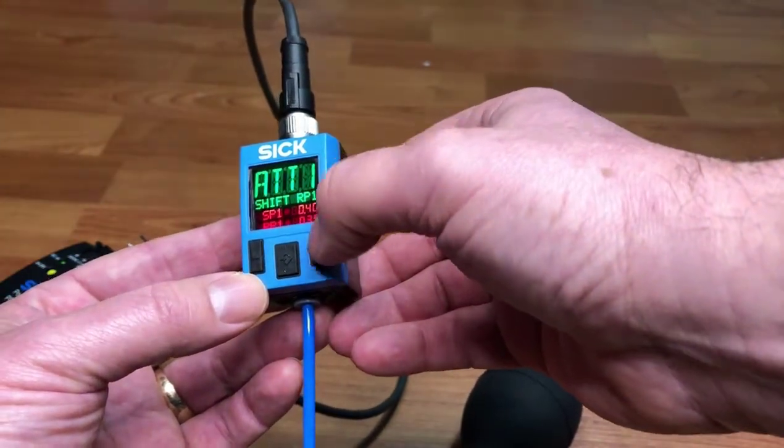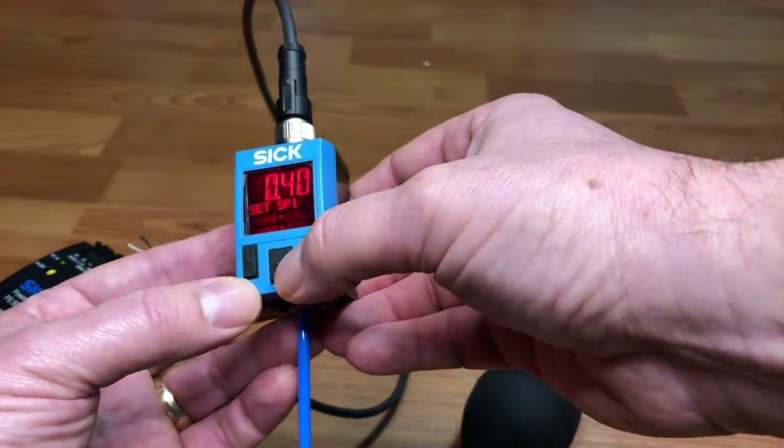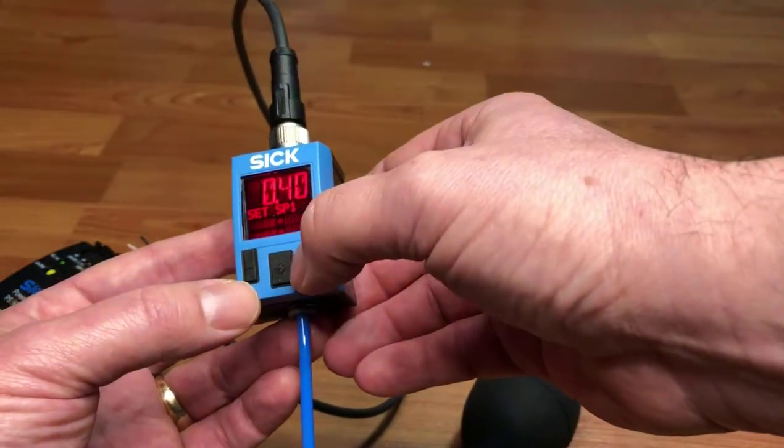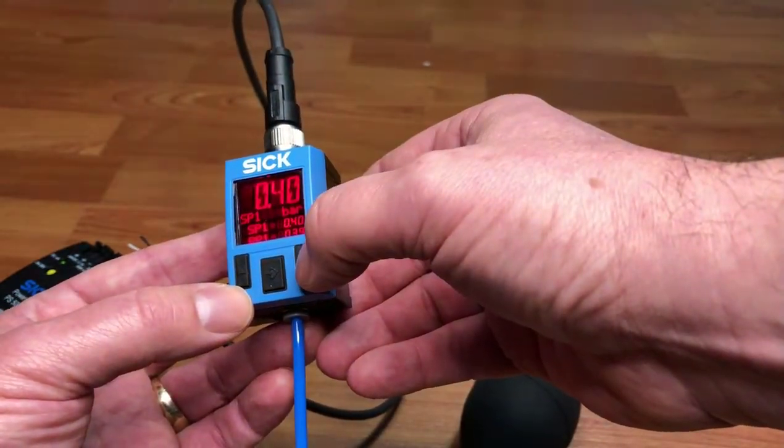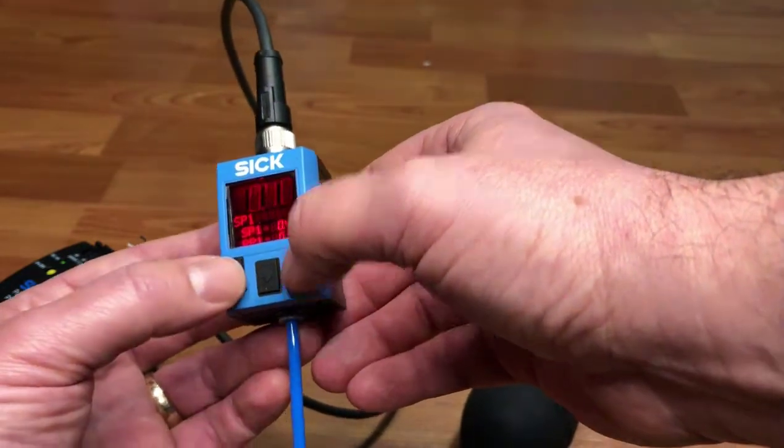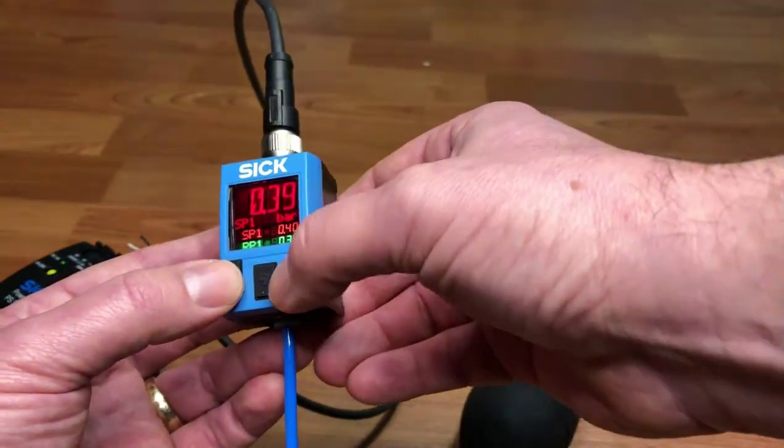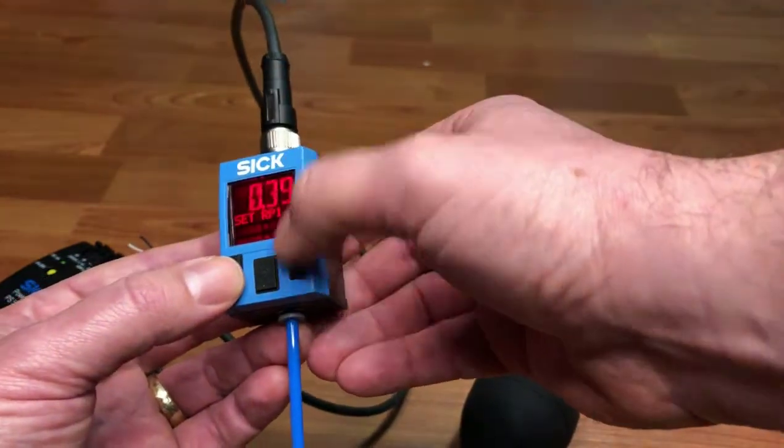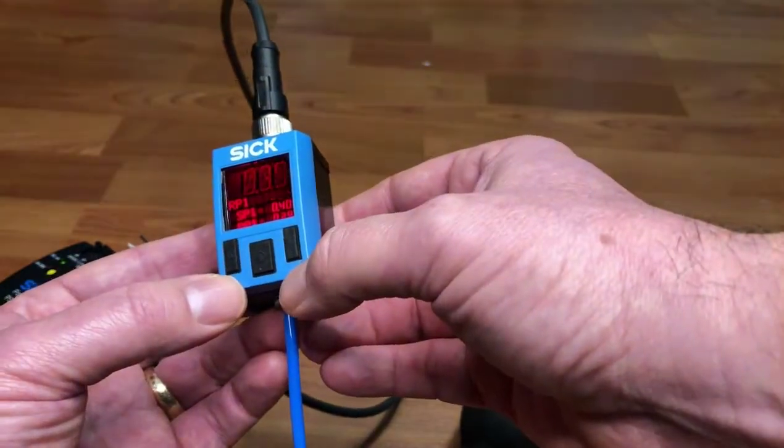We're going to get an attention message. It's basically because we need to shift the release point. The release point's really close—it's 0.39 and our switch point's 0.4, so we're going to adjust that release point. We're going to move the down arrow key instead of the release set point. We're going to change it to release point and press the middle key to go into the release point.